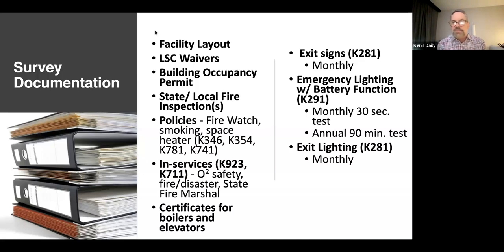And so again, you're testing that. Some of you may only have one of these. Some of you may have these throughout the building, at exits and different places in the corridors. No matter how many devices you have that have a battery in them, you have to test them once a month for 30 seconds or 90 minutes annually. And then emergency exit lighting kind of overlaps on this. You also have to have no less than 90 minutes of emergency exit lighting at every exit.